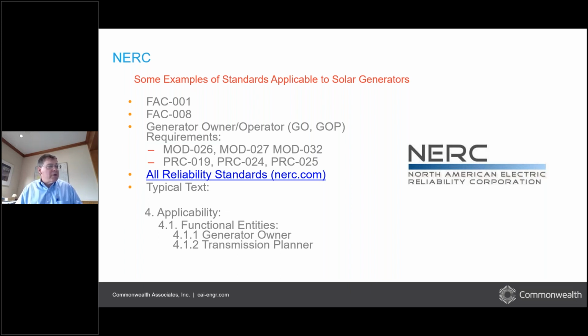Then there are a number of generator owner operator requirements. I've listed MOD-26, MOD-27, MOD-32, and some protection standards, PRC-19, 24, and 25. We'll talk about particularly 24 a little bit down the road. But these are standards where the application of them is unclear, at least, or I should say evolving, for solar operators. For example, 26 and 27, if you read them, you say, oh, okay, how do I apply this to a solar installation? It's talking about synchronous generators and a lot of that.